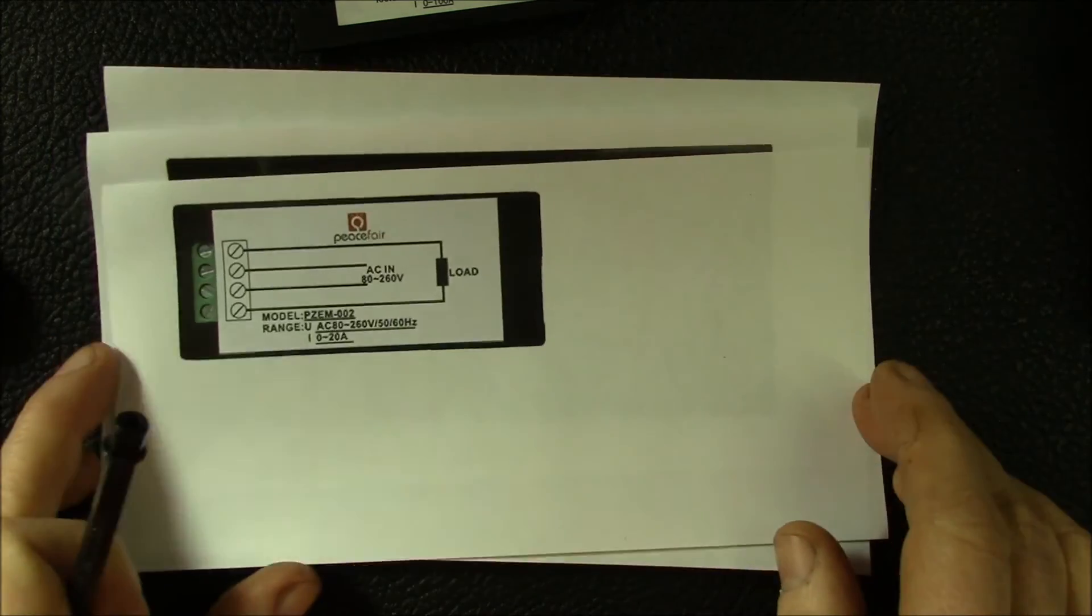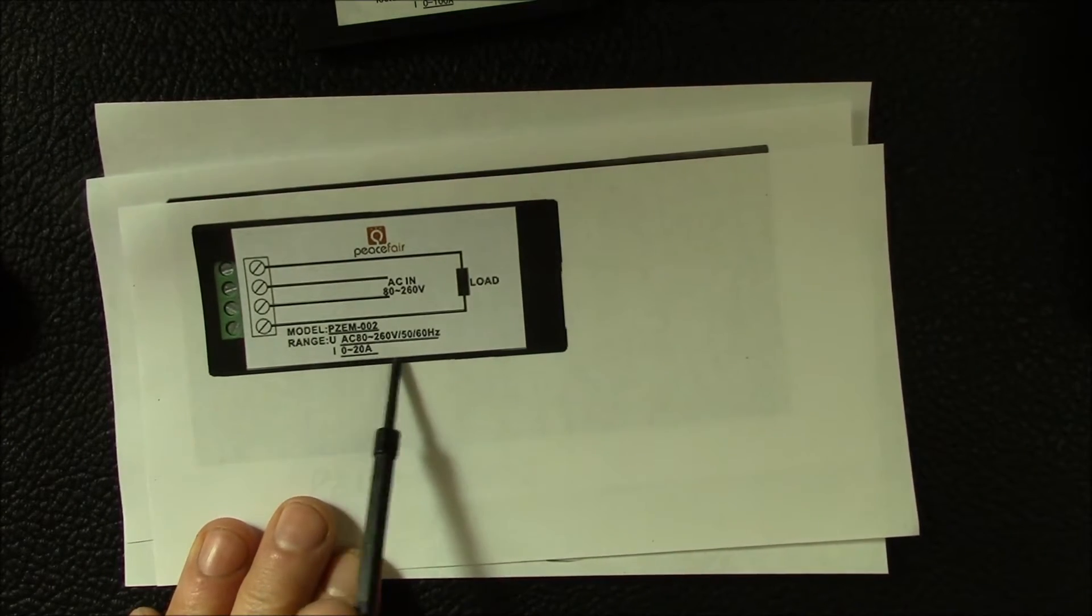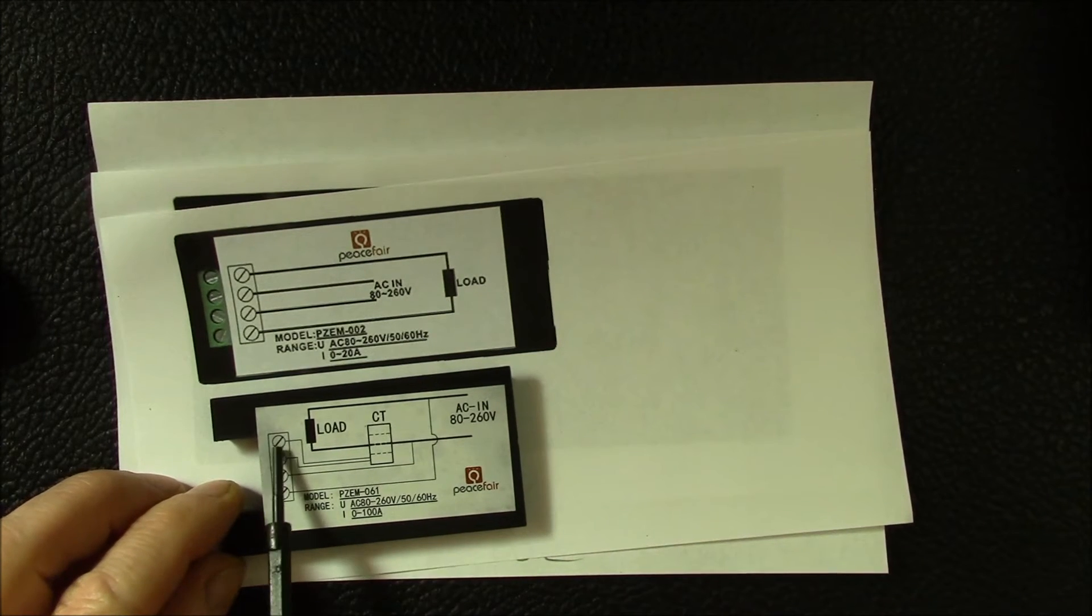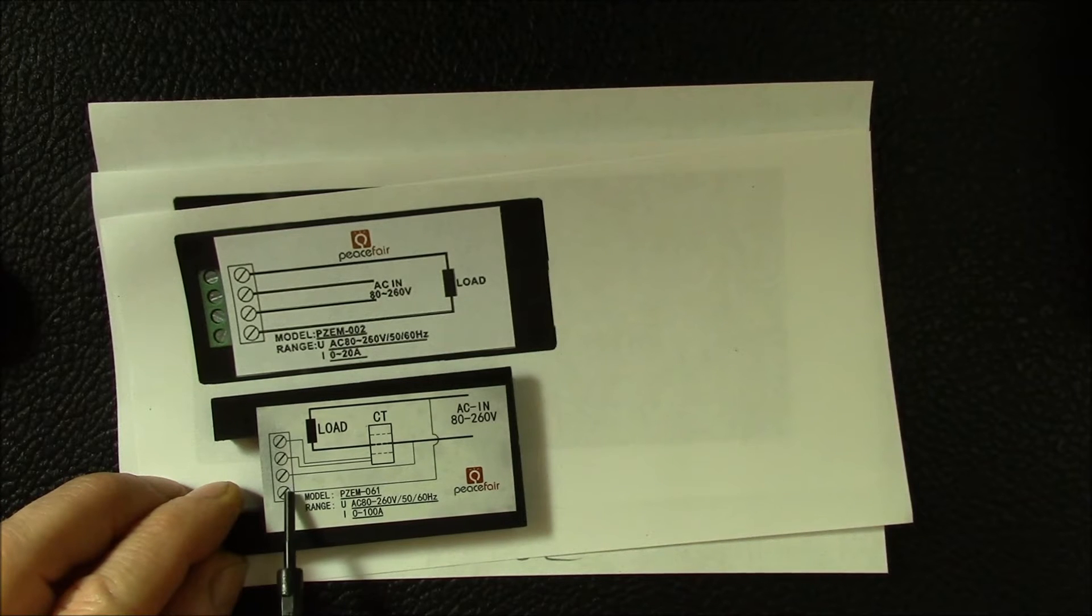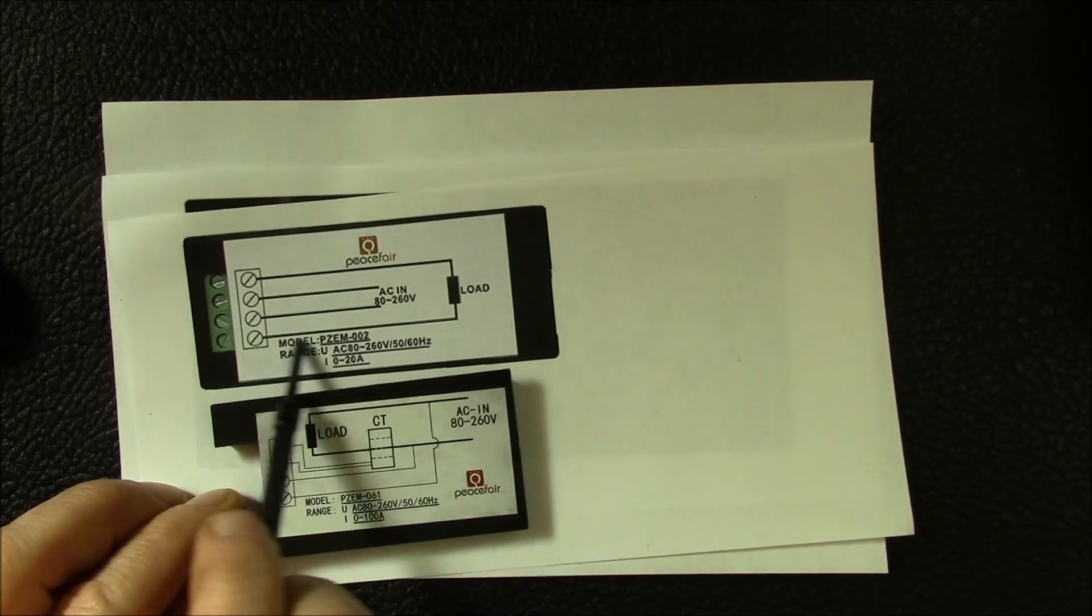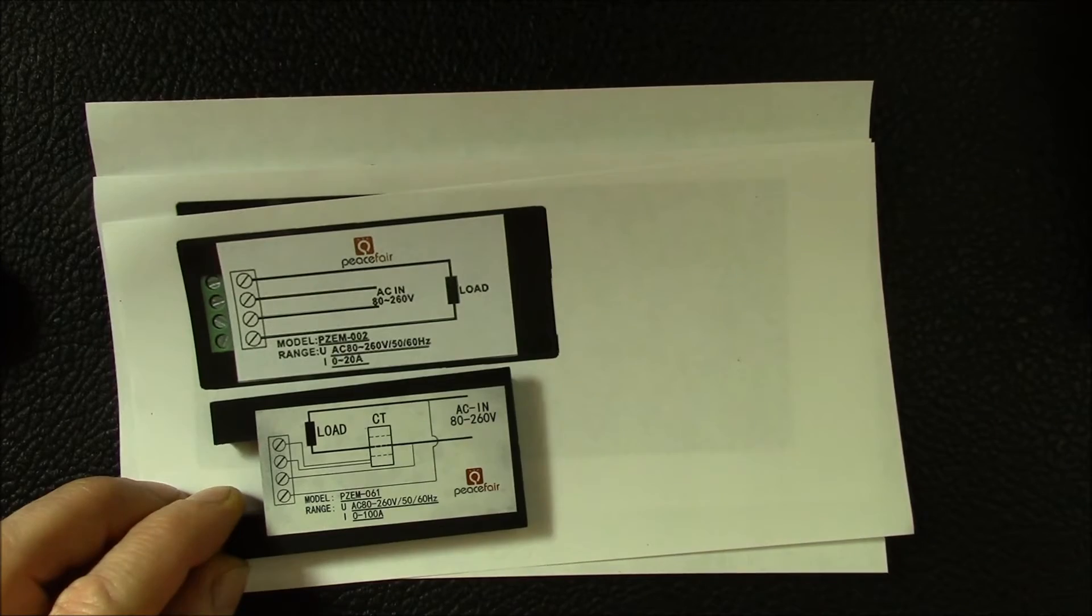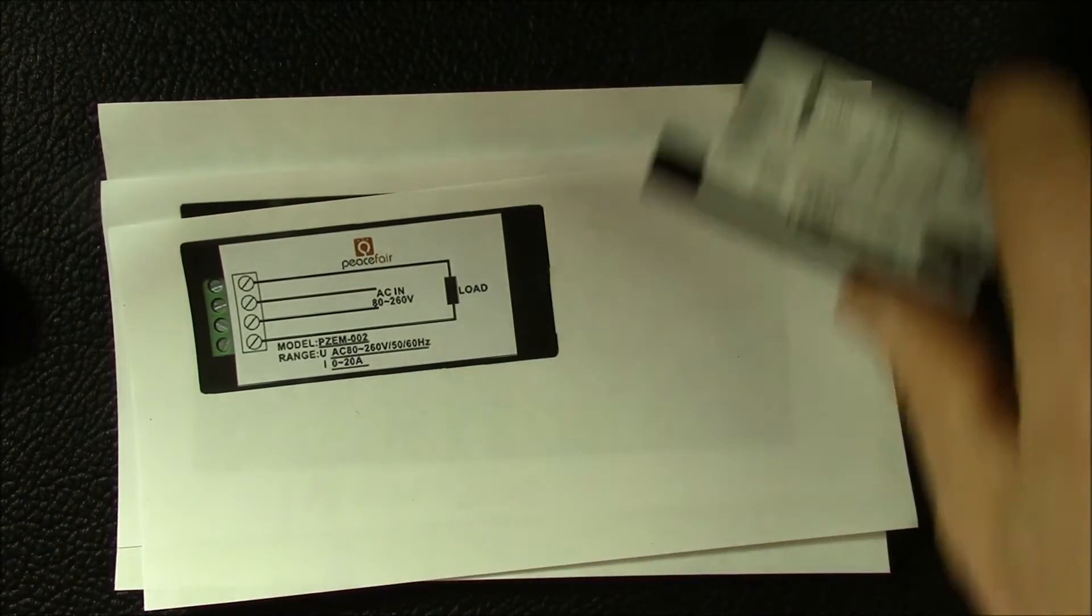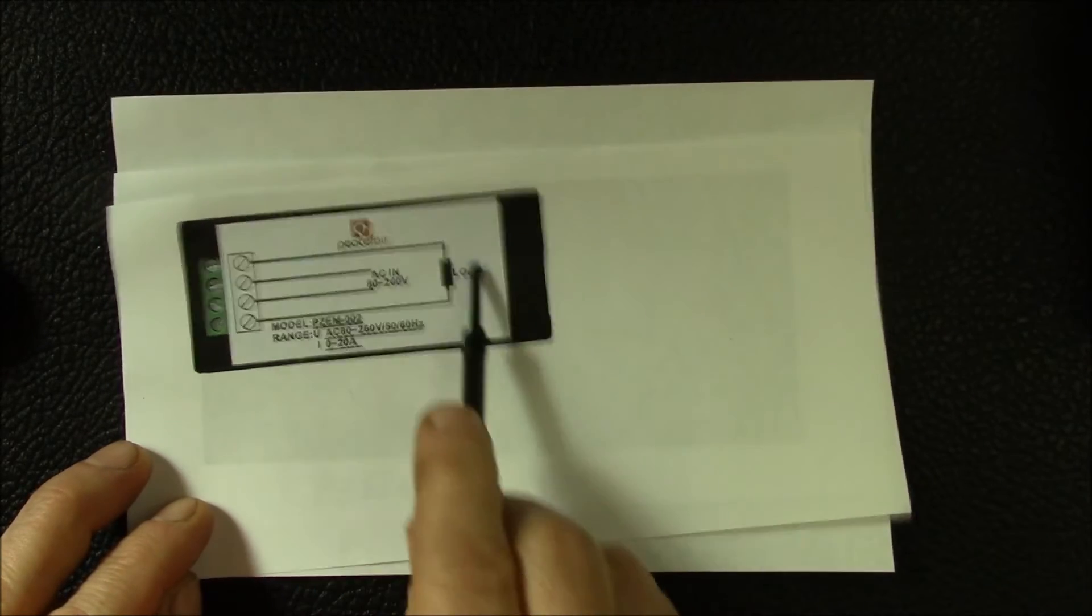The one thing you do need to be aware of with these variations is one of the 20 amp versions. If you notice here, the wiring is a little bit different. Here you had current transformer on the top, voltage on the bottom. This internal version has current flowing through the outer terminals and then voltage on the inner terminal. So you need to make sure you read the wiring diagram because they are different. This again is a 20 amp internal version, there's no external current transformer.